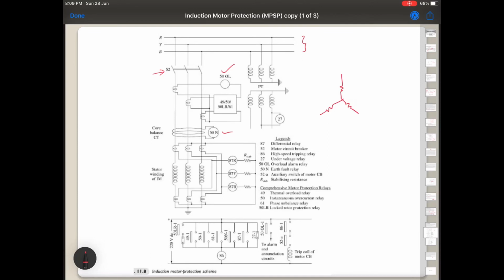Suppose this is the 3-phase of a motor. I have shown resistance instead of inductor, that's fine. So earth fault means this neutral must be given through a relay to the ground. And what is an earth fault? For example, when it is unbalanced, suppose here you have 10 ampere, I am taking just an example, and here you have 6 ampere, and here say 7 ampere. Actually these two are incoming.